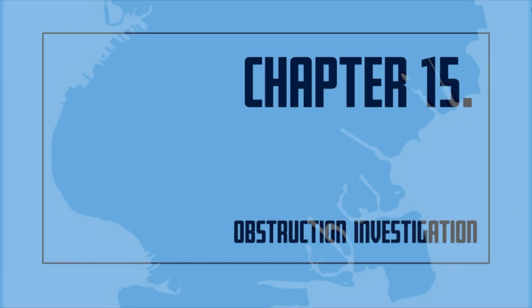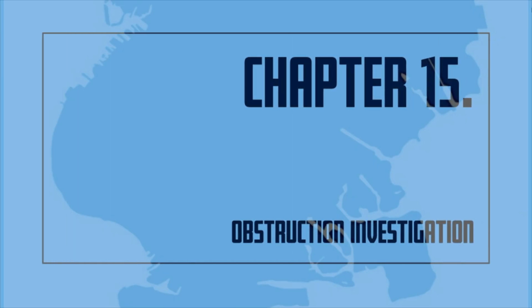Chapter 15. Obstruction Investigation. The presence of obstructions in sprinkler systems shall be checked every 5 years by opening a flushing connection at the end of one main per system. One sprinkler head per system toward the end of one branch line shall also be removed. This is done for investigating for the presence of foreign organic or inorganic material.